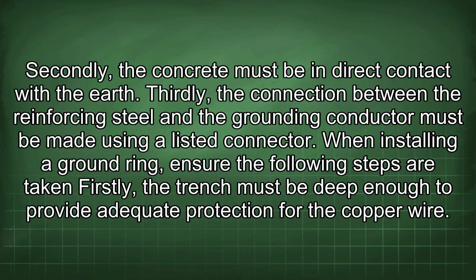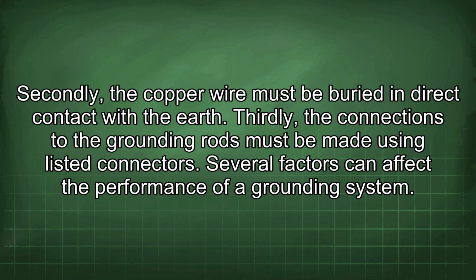When installing a ground ring, ensure the following steps are taken. Firstly, the trench must be deep enough to provide adequate protection for the copper wire. Secondly, the copper wire must be buried in direct contact with the earth. Thirdly, the connections to the grounding rods must be made using listed connectors.